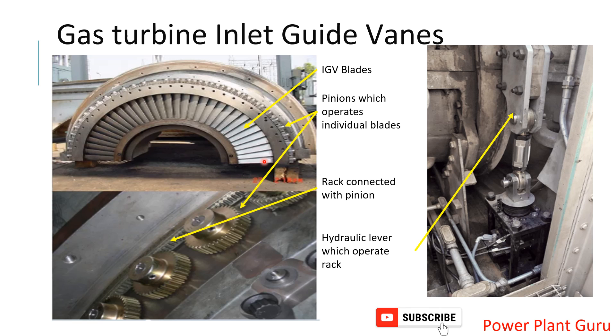Many people get confused with the IGV opening percentage. IGV opens from around 34 to 84 or 86 degrees — wherever we see the opening value, it is in degrees, not percentage. So 34 degrees is the minimum opening and 84 or 86 degrees is the full opening. This is how the IGV operates.